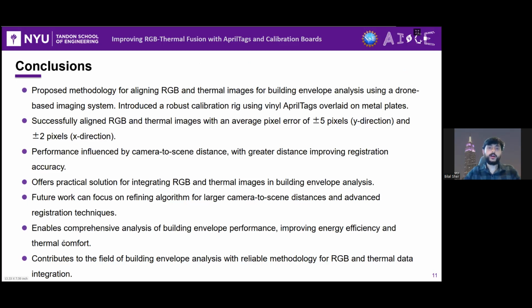To sum it up, to conclude, this methodology can be used for aligning the thermal and the RGB images for the purpose of building envelope analysis using a drone-based imaging system. We have introduced a robust calibration rig using the vinyl April tags overlaid onto a metal plate. It's something that can be shipped onto site and used in the field. There's no worry about damaging it, and it does not need any sort of passive or active heating. The algorithm that we use aligns RGB and thermal images with an average pixel error of plus or minus 5 pixels in the Y direction and plus or minus 2 in the X direction.